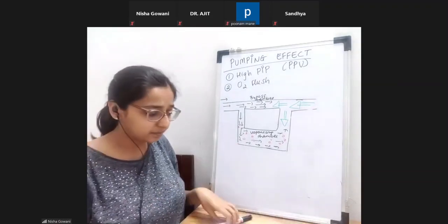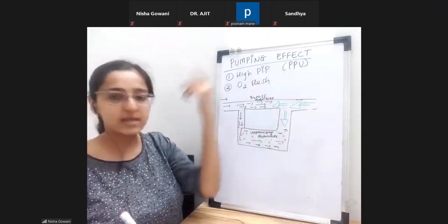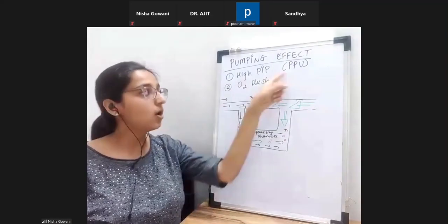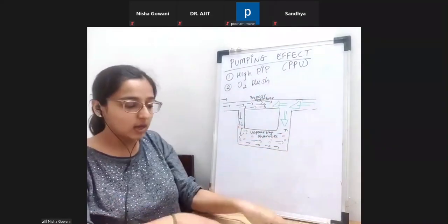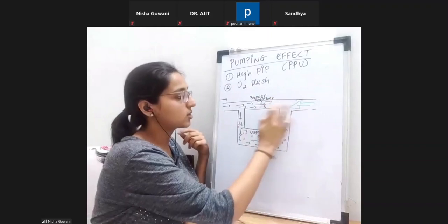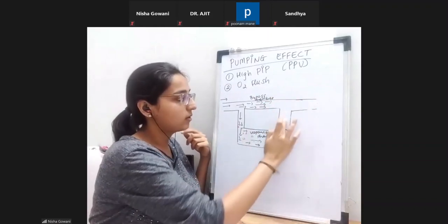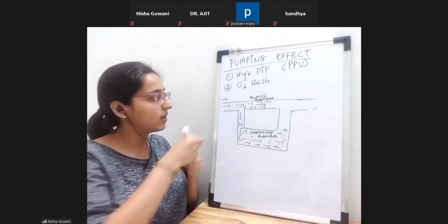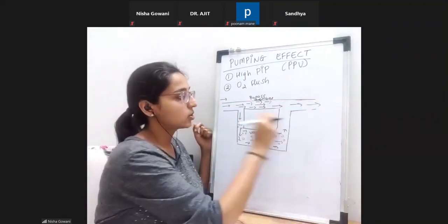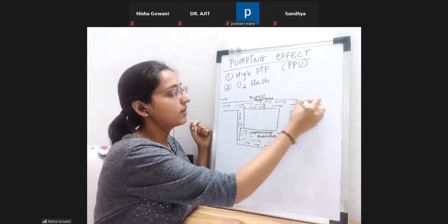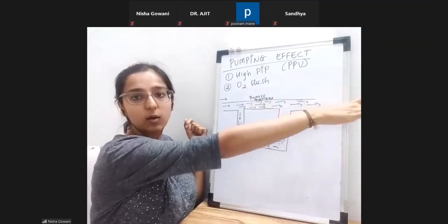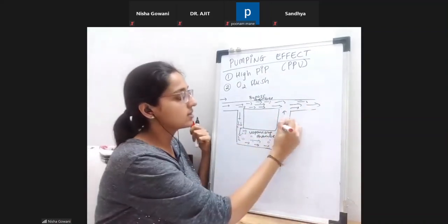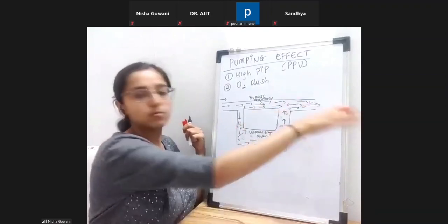Now I have released the pressure. Now positive pressure, the inspiration, is done. I have released the oxygen flush, for example, or now I have entered the expiratory phase. So this back pressure is gone, right? Now what will happen when the pressure is suddenly gone? There will be fast movement like this. So whatever gas was collected in the bypass chamber will start moving out. Same here, the vaporizing chamber also will start moving out. All these gases along with the vapors are going to start moving out.